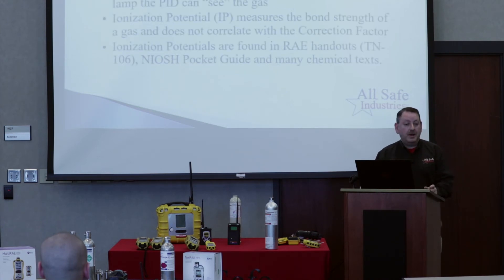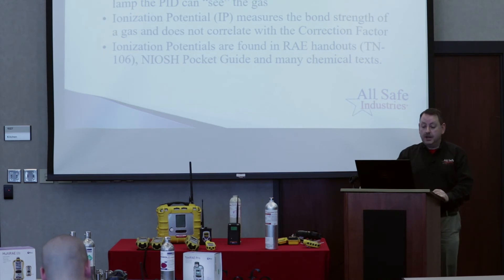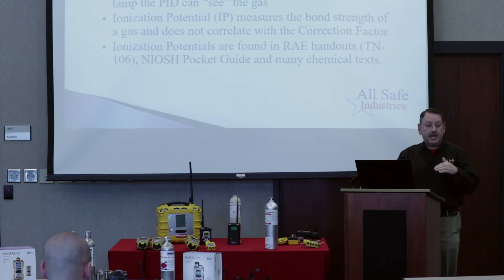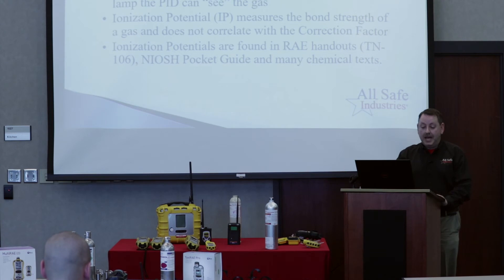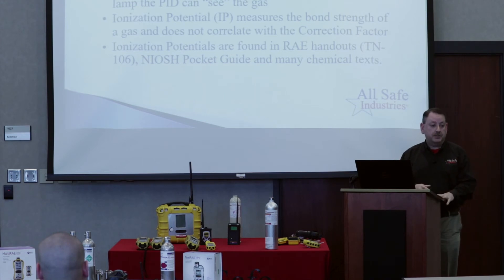Let's talk more about ionization potential. This is very important if you're responding to a call and you know you have a volatile organic compound you're dealing with. The IP — that number in parentheses — tells us if our PID sensor can read that gas or not. It's also known as ionization energy. If the IP is less than the output of your PID lamp, then our PID can see that gas. The ionization potential measures the bond strength, and as long as the ultraviolet light in our PID is stronger than the bond of the chemical, we can break that open and read that particular gas.